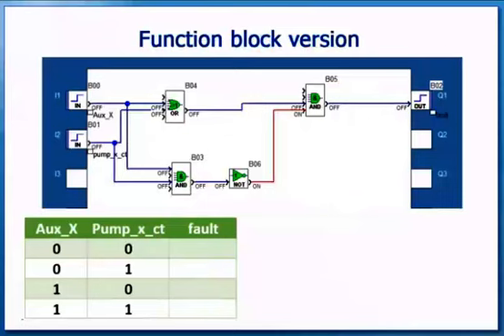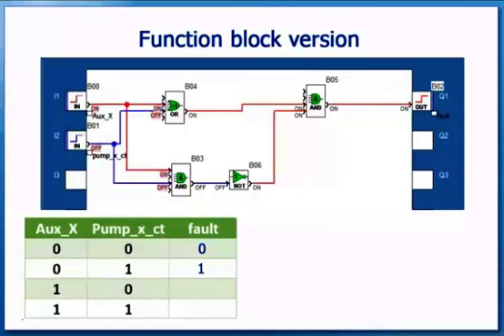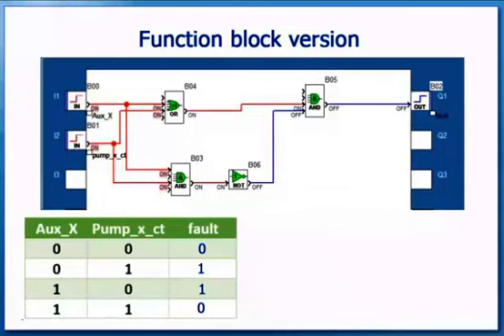Here is the function block version. We can step through its function and prove that the truth table is correct. There are no internal relays — that function is performed by the interconnections between the function blocks. Both inputs off: fault indicator off. Auxiliary X off and PUMPXCT on: fault indicator on. Auxiliary X on and PUMPXCT off: fault indicator on. Both inputs on: fault indicator off. The truth table is the same, so the program works.